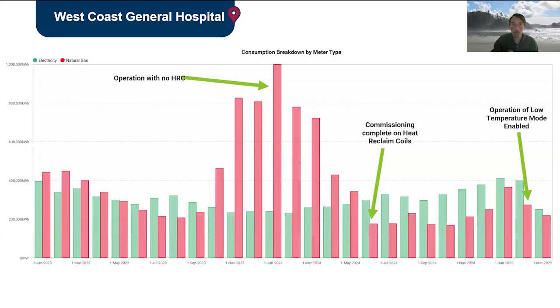So the large red bars give us a really good baseline to compare against. In May of 2024, we implemented the heat reclaim coils. You can't necessarily see that because now we're starting to transition into summer state of operation, but you can see that benefit when you look at November of 2024 or December of 2024 in comparison. You'll see a 50, 60% drop on those bars. But the recent change is actually a little bit hidden here, because February of 2025, the last call out there, was actually a colder month than January. So you would compare that February 2025 against the highest bar here, January 2024, to see how far we've come on this journey.